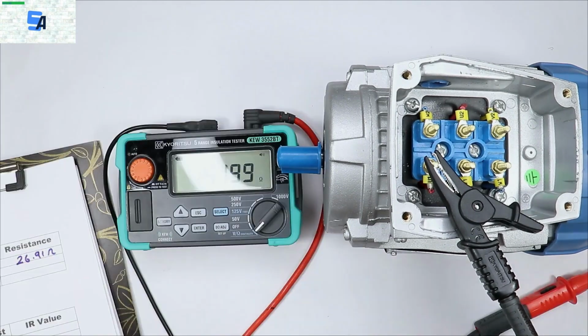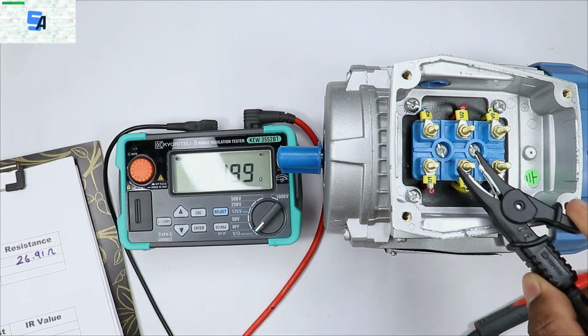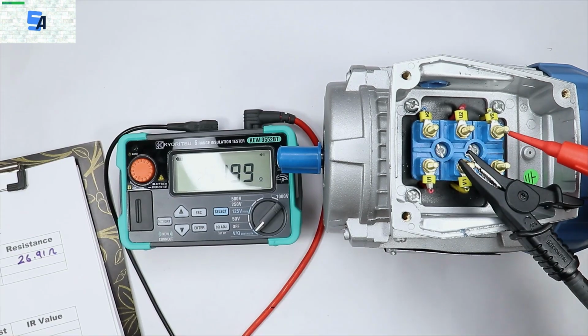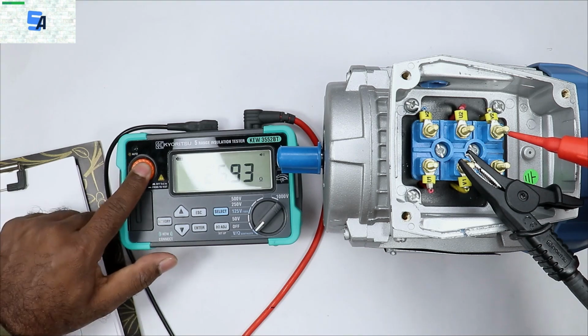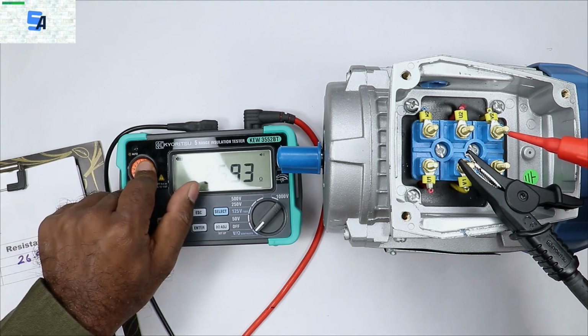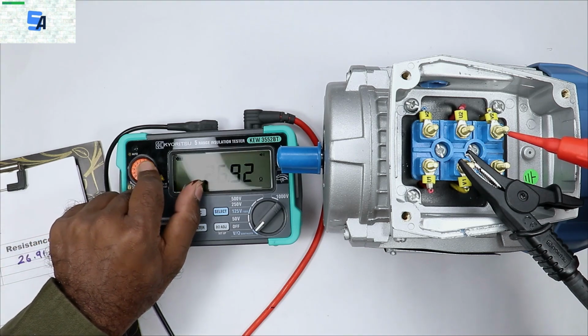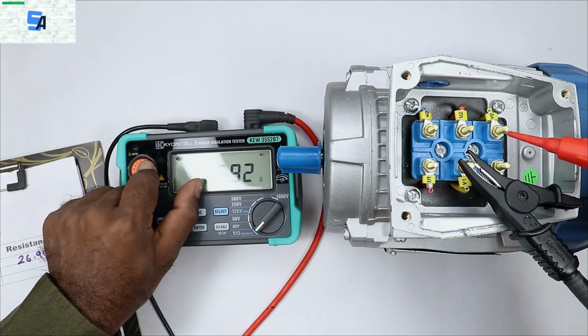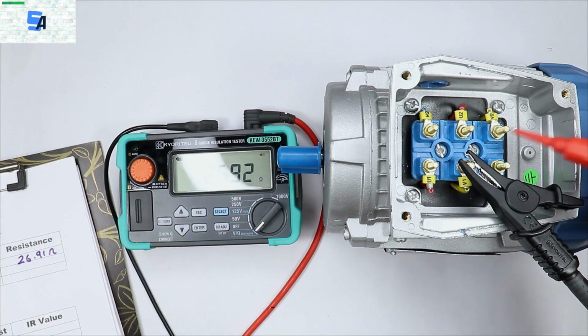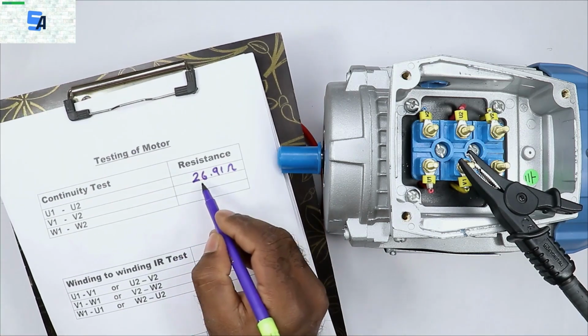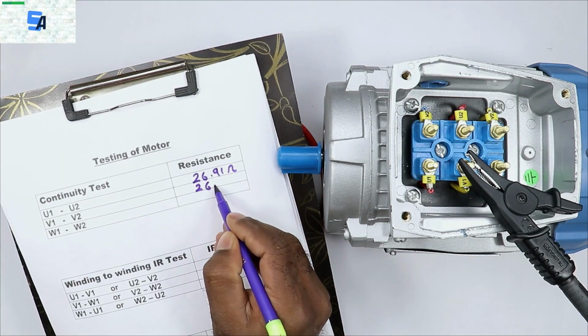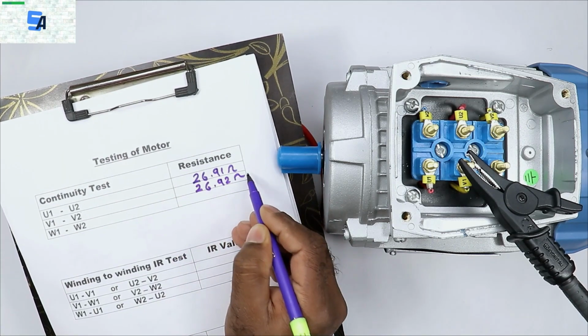Now after this, what we have to do, this other winding here, V1 and V2 winding, with this winding connect the probes and press the test button in the insulation tester. On pressing the button, the value will be displayed on the screen. 26.92 ohm resistance we are getting. So I am noting down this value also. We are getting resistance here as 26.92 ohm.